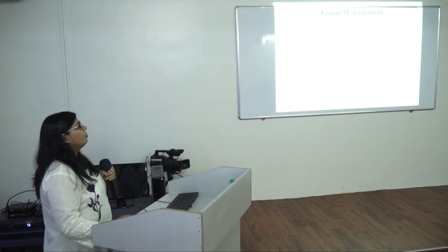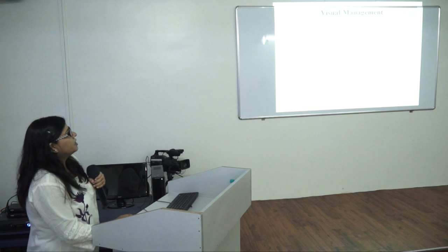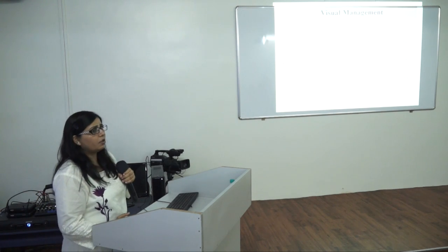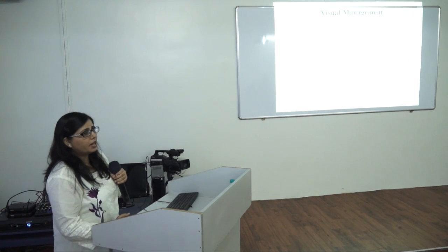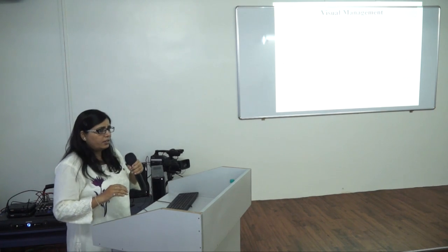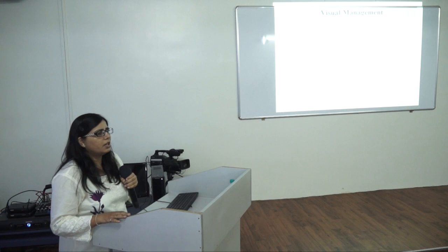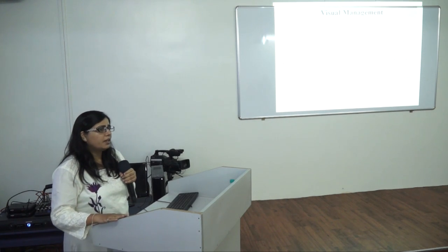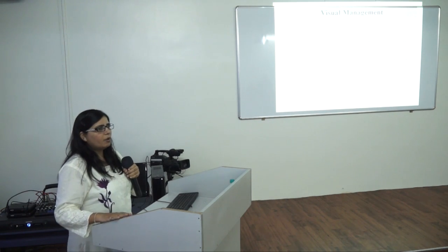When user inspections were done, display alarms and thermometers were not there, so we provided the display alarms and thermometers. SOPs and charts were also not there.